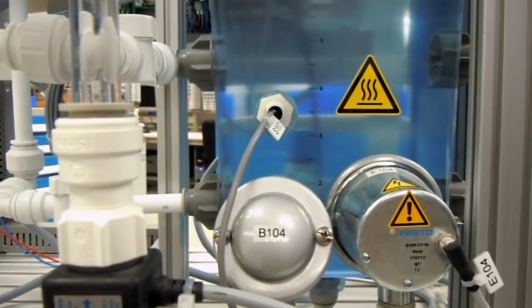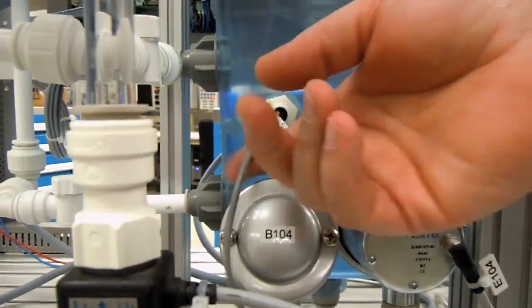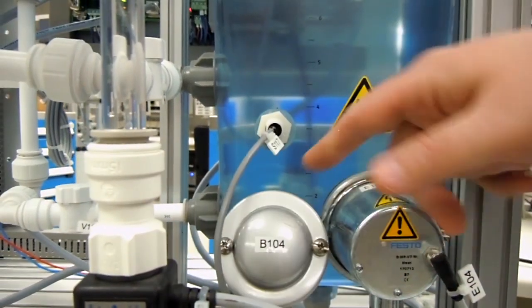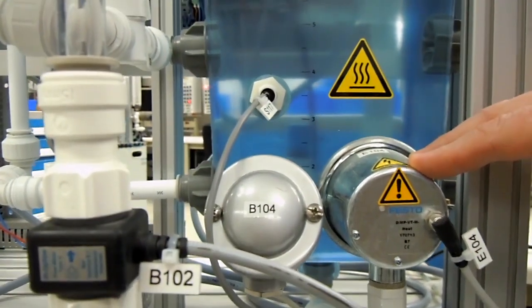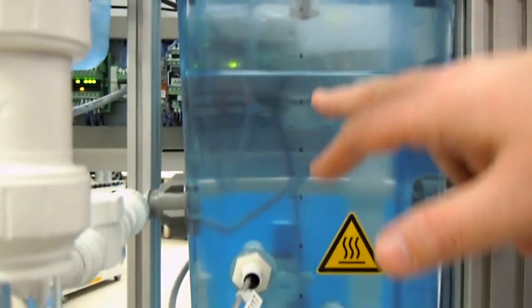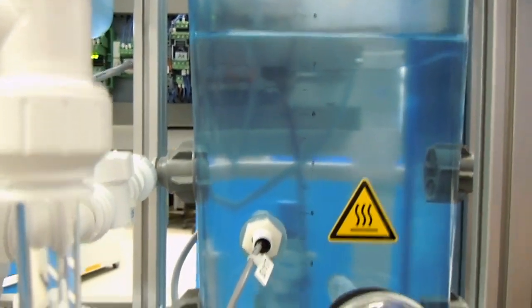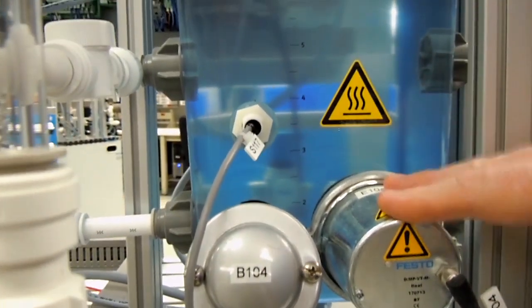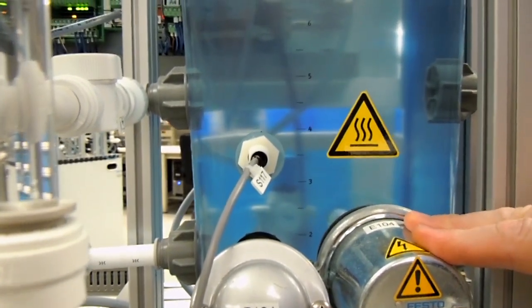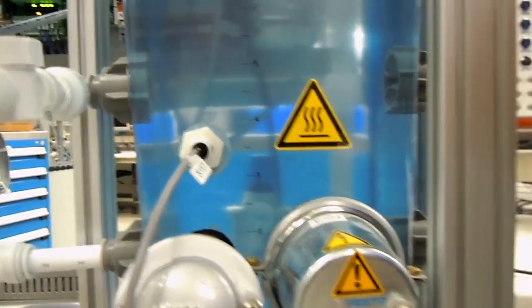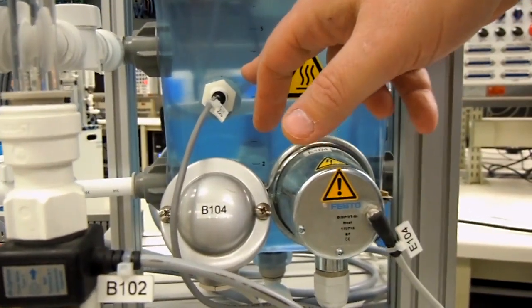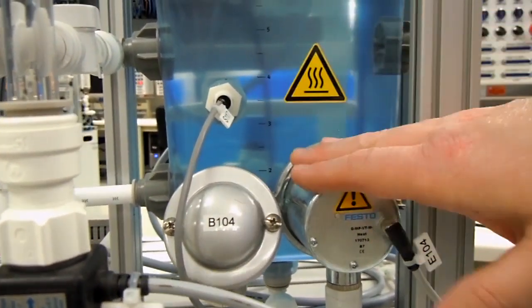There are 3 floats on the Festo system. S117 doesn't actually connect to any of the electrical signals. It's a safety float so that when the level in this tank goes below that float, it actually cuts off the heater. Because if there's no water in here, you don't want to be running that heater. So it doesn't go back to the Festo system or the software on the screen. When it drops down below, it turns this heater off.